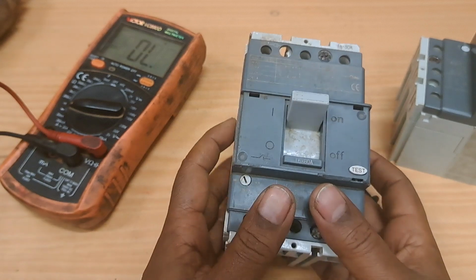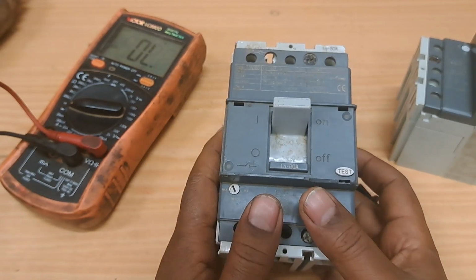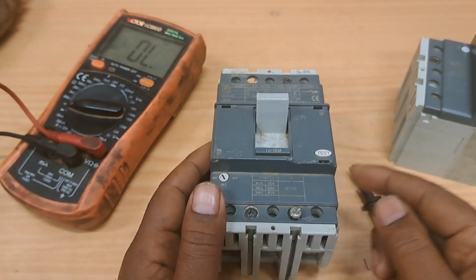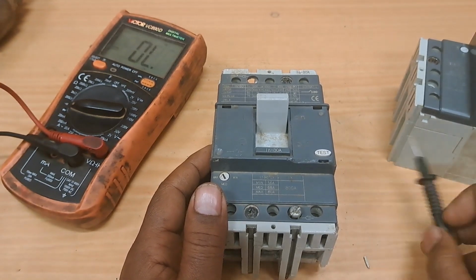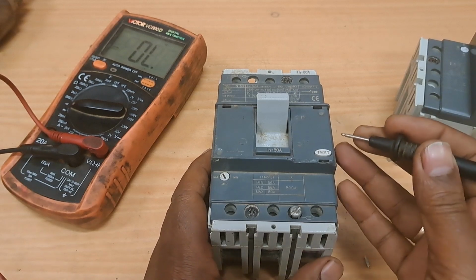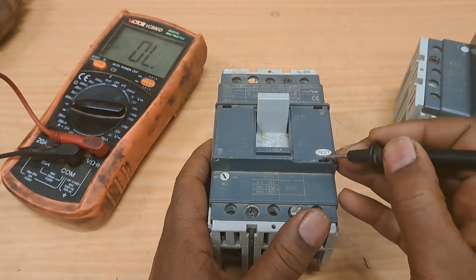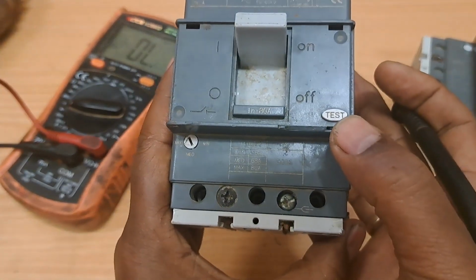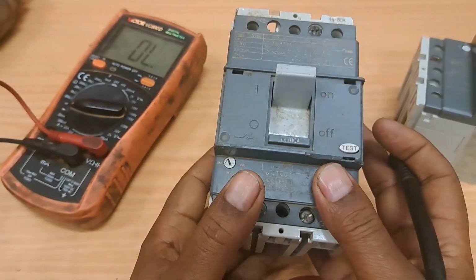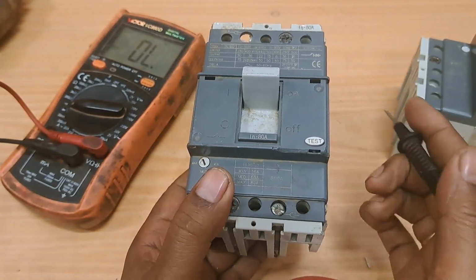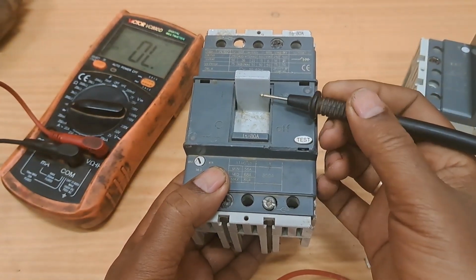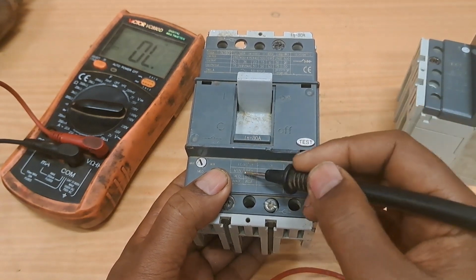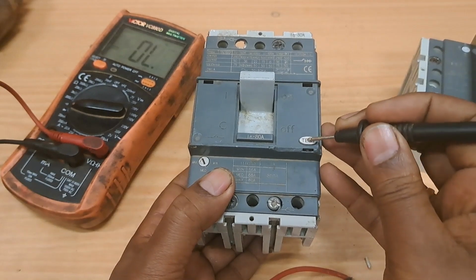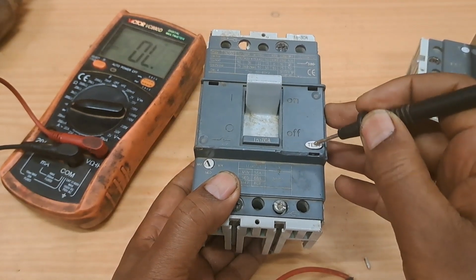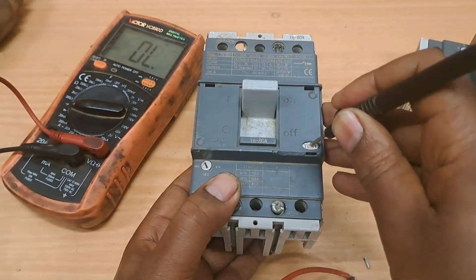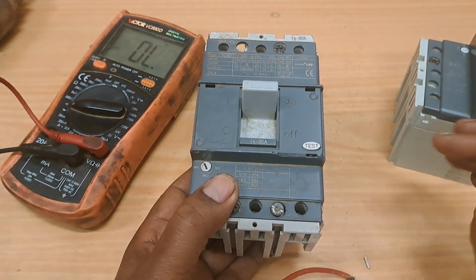And finally, the final test is the trip test. If you want to see if the breaker will trip when electric current exceeds the maximum value, simply put it in the on position and press this test button. If you see right here, there is a test. You press on the test and it should trip. It should turn off. If it trips, it means this circuit breaker is functioning properly, and it can trip when there is excess current. Let's go ahead and try that. See? Now it has tripped.